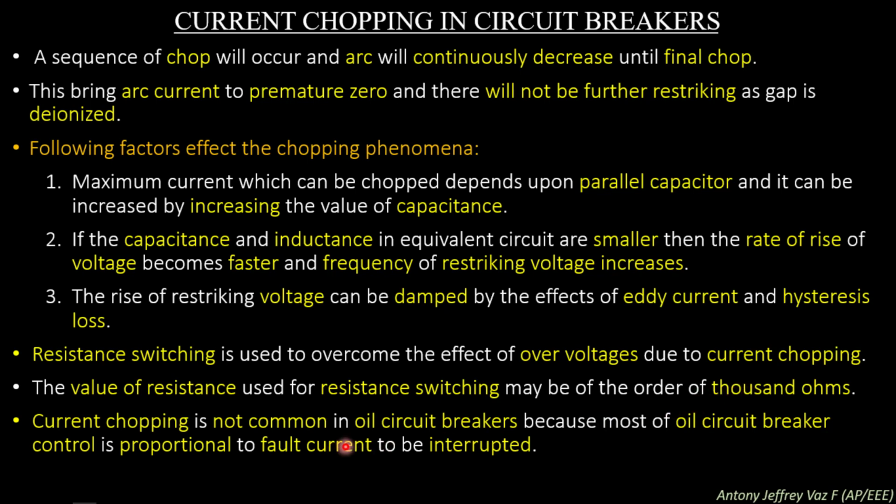Current chopping is not common in oil circuit breakers because in most oil circuit breakers the extinguishing power is proportional to the fault current to be interrupted. So this current chopping phenomenon occurs in vacuum or air circuit breakers.